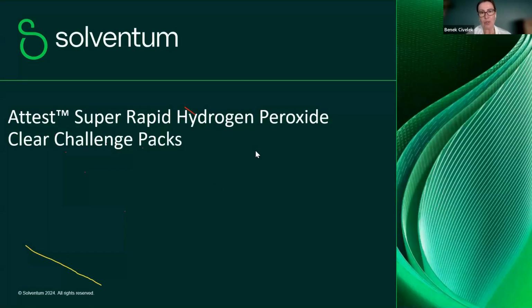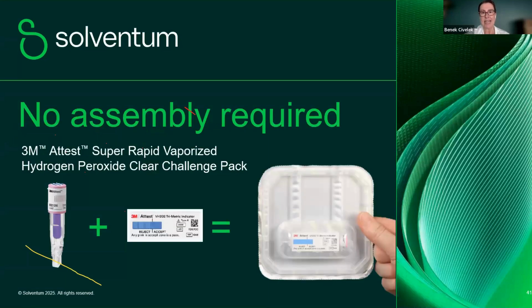When talking about load control, at the beginning we said that we are going to introduce you to some new technologies. The first one is the super rapid hydrogen peroxide clear challenge pack. We are familiar with process challenge devices, because the guidelines recommend using process challenge devices which have a BI and a CI inside, to challenge the sterilant and have the best sterilizing conditions. This system is called a clear challenge test pack. As you can see, it's transparent. It has a biological indicator for hydrogen peroxide together with a type 4 indicator, again designed for hydrogen peroxide.